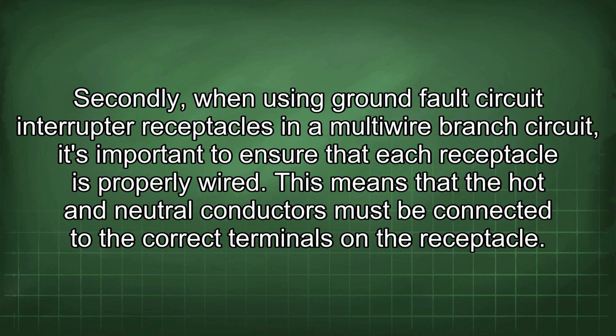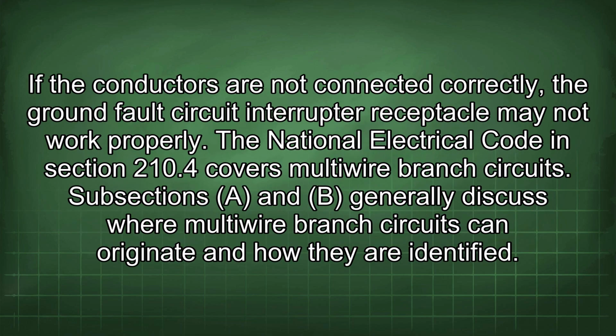Secondly, when using ground fault circuit interrupter receptacles in a multi-wire branch circuit, it's important to ensure that each receptacle is properly wired. This means that the hot and neutral conductors must be connected to the correct terminals on the receptacle. If the conductors are not connected correctly, the ground fault circuit interrupter receptacle may not work properly.